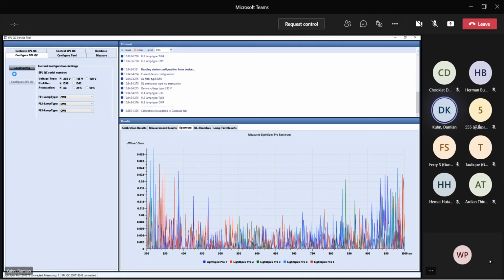But as soon as you click on load configuration, it's going to connect to the SPLQC device and it will show you the configuration on your actual connected instrument. So now you can see the instrument serial number and the fluorescent lamp setup. So basically, as I was mentioning before, on old instruments you will probably not have any LED light source available for selection directly on the instrument screen. And that is really because the available light sources are not really stored in the firmware.